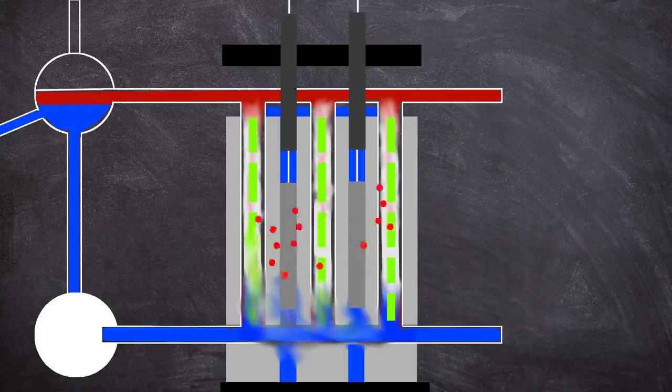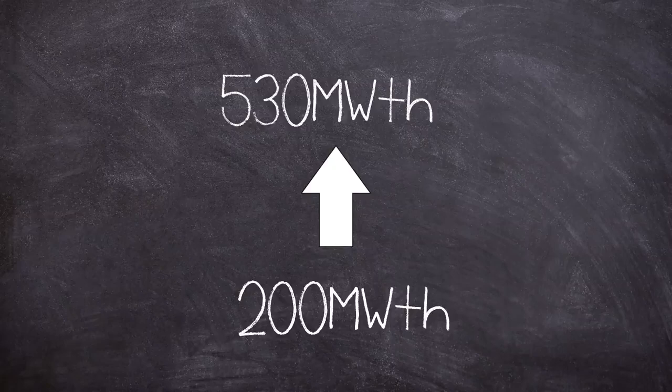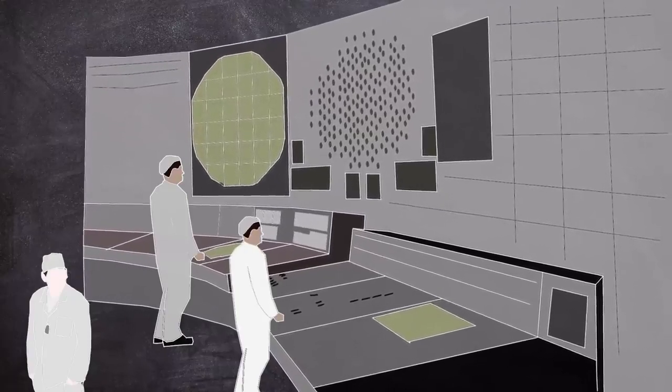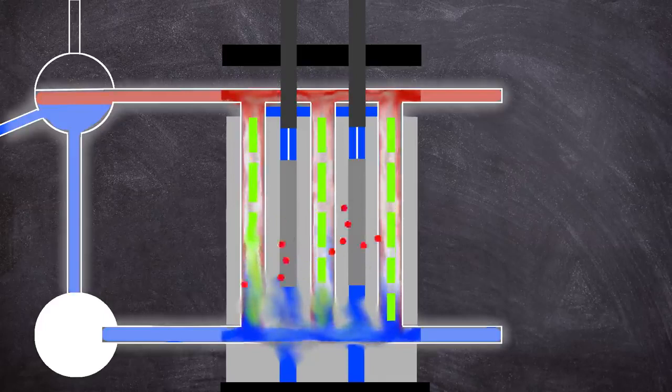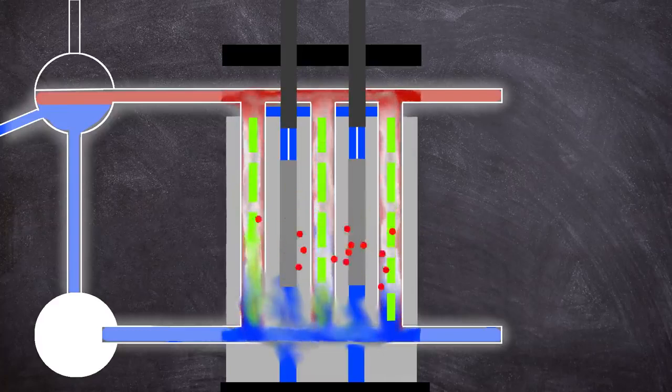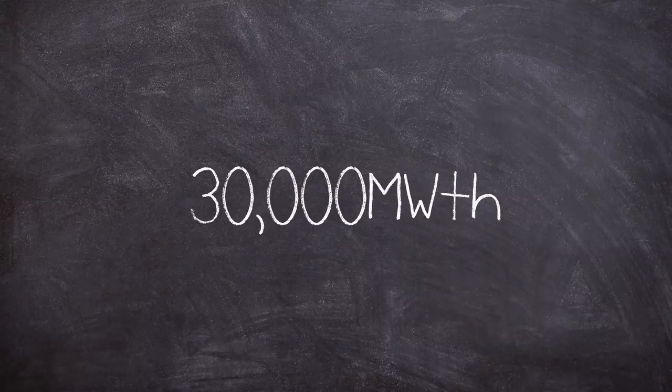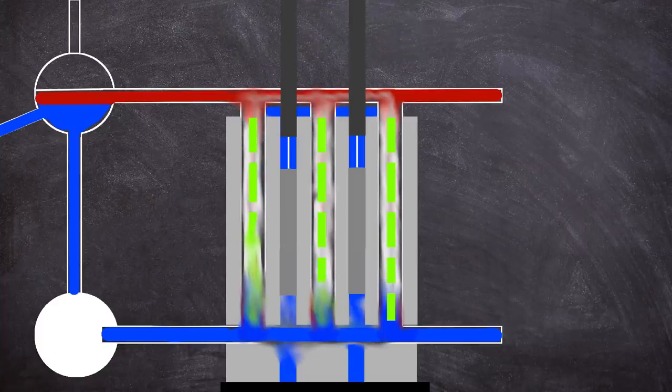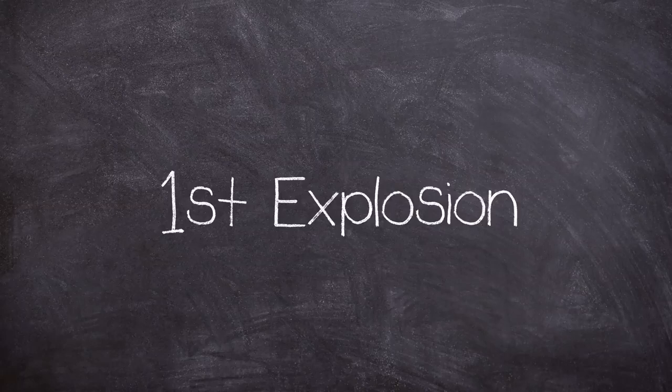This left the graphite water displacers stuck in the lower part of the core, increasing the runaway power excursion. Within three seconds, the reactor power rose to 530 megawatts of thermal energy. In the control room, a few shocks were felt, and the control rod indicators showed that insertion had stopped. As the channel pipes began to rupture, mass steam generation occurred as a result of depressurization of the reactor cooling circuit. Fission materials leaked into the coolant and steam pressure grew inside the core as coolant boiled off, creating a greater neutron population. The reactor power hit 30,000 megawatts of thermal energy, although it is thought the power could have gone much higher. The steam blew off the top steel cover and top biological shield of the reactor as more than the two designed fuel channels failed, releasing debris into the reactor building. This was what would later be described as the first explosion.